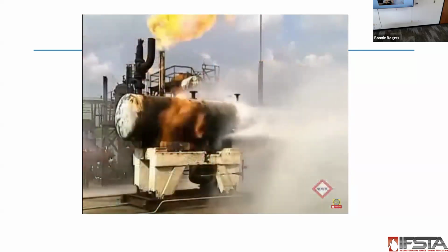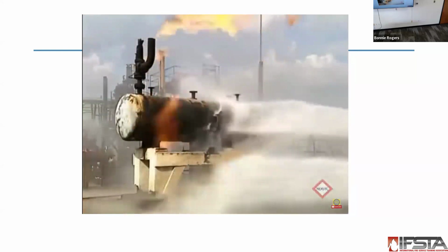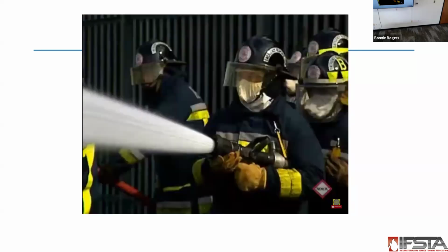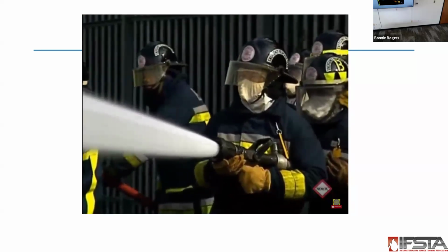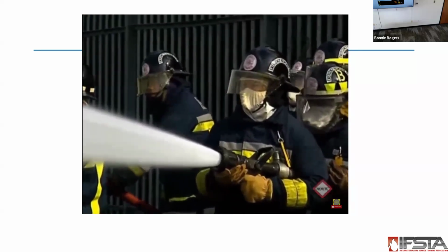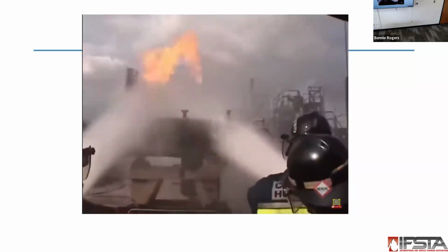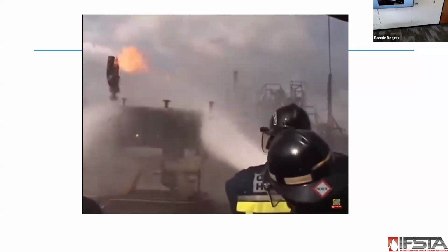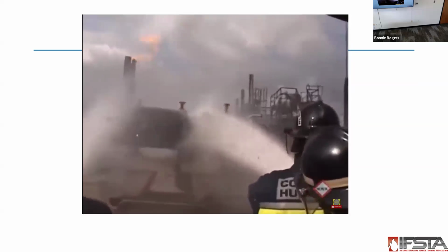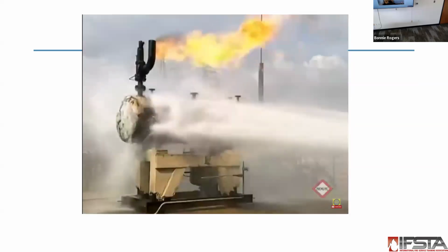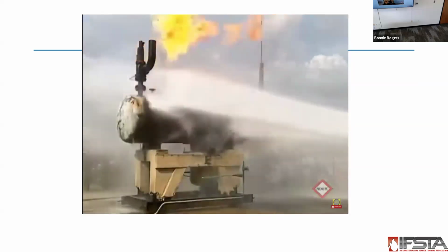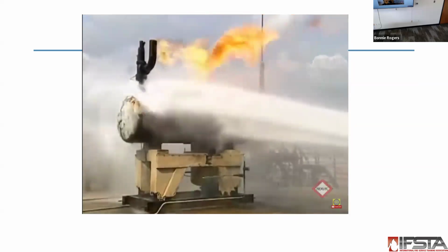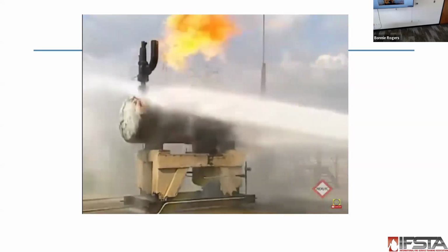In the event of fire, tanks containing highly flammable liquids or gases are sprayed with water to cool the tank and its contents. These pictures show fire auxiliaries at ConocoPhillips Humber Refinery practicing dealing with fires around fixed tanks and vessels. They're not only cooling the vessel, but trying to stop the flaming product escaping from the pressure relief valve, impinging on the tank.